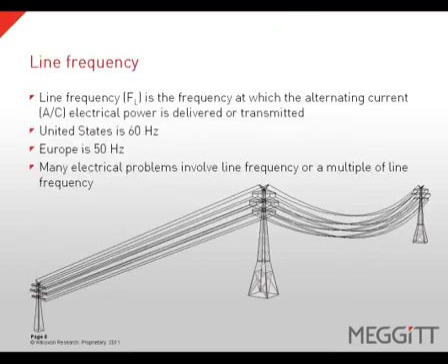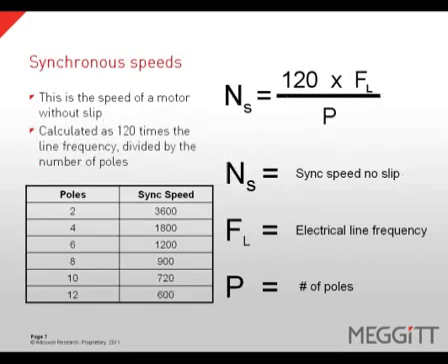Line frequency is the frequency at which alternating current, or AC current, electrical power is delivered or transmitted. In the United States, this is at 60 hertz. In Europe, this is at 50 hertz. Many electrical problems involve line frequency or a multiple of line frequency. Synchronous speed is the speed of a motor without slip. Slip is the difference between the synchronous speed and the actual speed of a motor. We can calculate synchronous speed by multiplying 120 times the line frequency divided by the number of poles. In the United States, a synchronous speed can be calculated by multiplying 120 times 60 hertz divided by the number of poles.